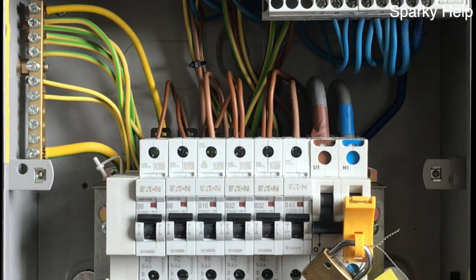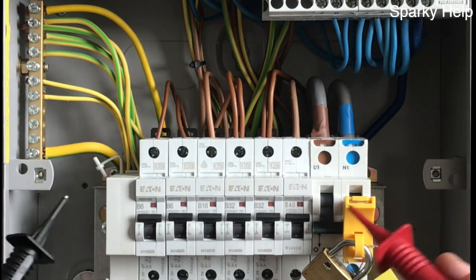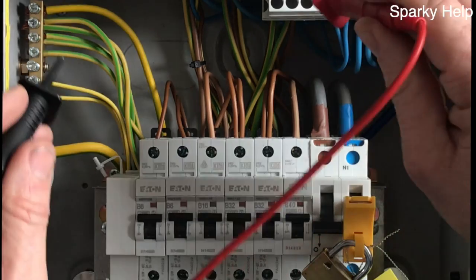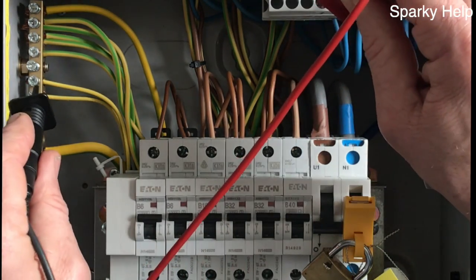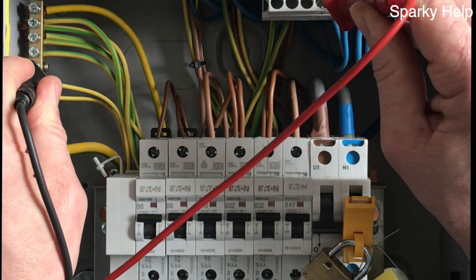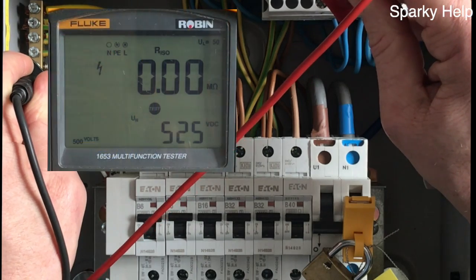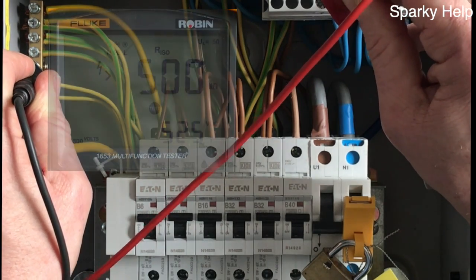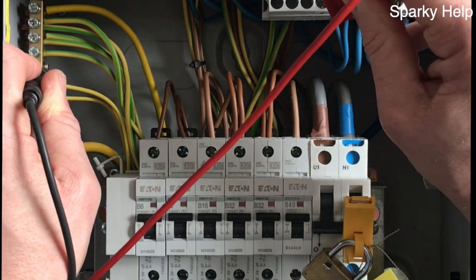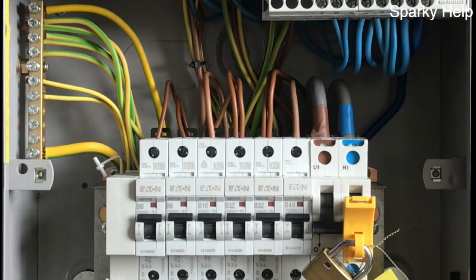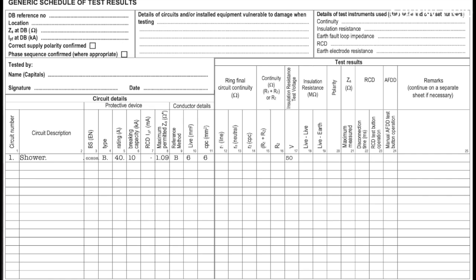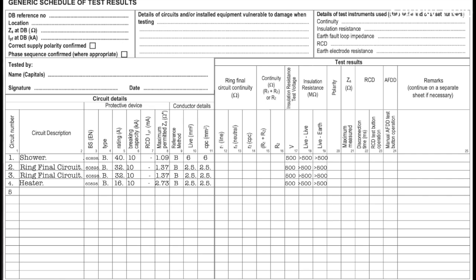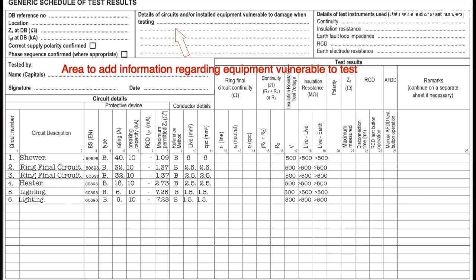We can now test neutral to earth is the last one. Now, again, unless you've got switching in the neutrals, and they need to be switched for a particular reason, that should be sufficient for that. And as you can see then, we've got greater than 500 for every single circuit. So now when we write it on the test sheet, that greater than 500 can now appear across every single circuit and every possible combination.